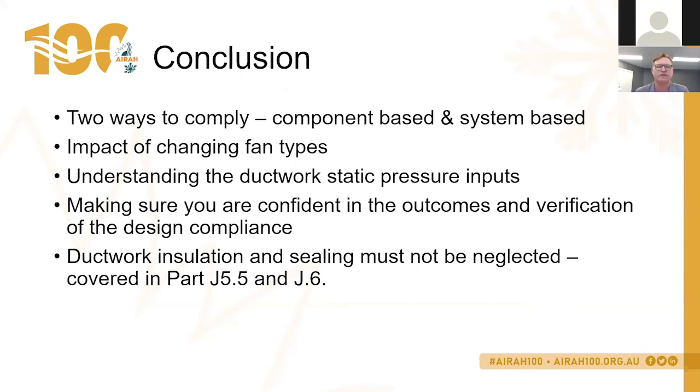So yes, it is something to take into account and note. Basically, the Building Codes Board note turning vanes to be a fouling risk. They do not state anything in regards to stream splitter dampers, VCDs, etc., but they do state that any fouling risk should be noted in the system.